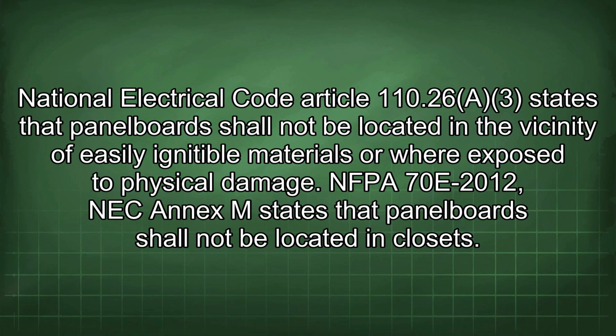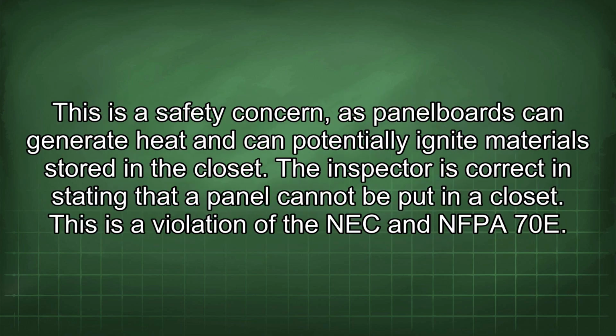National Electrical Code Article 110.26(A)(3) states that panelboards shall not be located in the vicinity of easily ignitable materials or where exposed to physical damage. NFPA 70E-2012, NEC Annex M states that panelboards shall not be located in closets. This is a safety concern, as panelboards can generate heat and can potentially ignite materials stored in the closet.